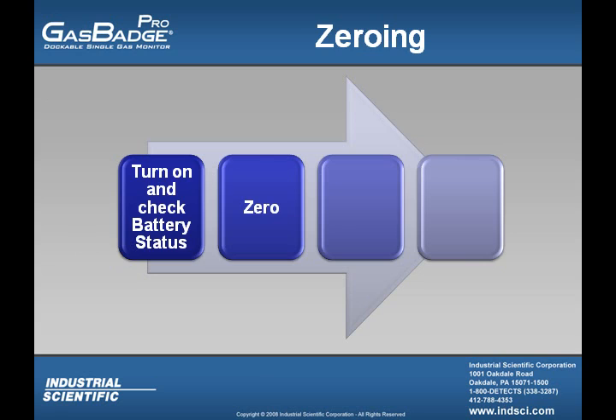The second step of operation is to zero the instrument. What zeroing means is that you're giving the sensor a baseline to know what fresh air looks like. For example, I'm going to zero the instrument so that my toxics will read 0 in a fresh air environment. And if I have an oxygen sensor in my GasBadge Pro, that sensor will calibrate to the concentration of oxygen within a fresh air environment. The most important thing that I can tell you, the user, is that when zeroing, make sure to zero the instrument only in a fresh air environment. If the GasBadge Pro is zeroed in a non-fresh air environment, then the sensor readings will be skewed.